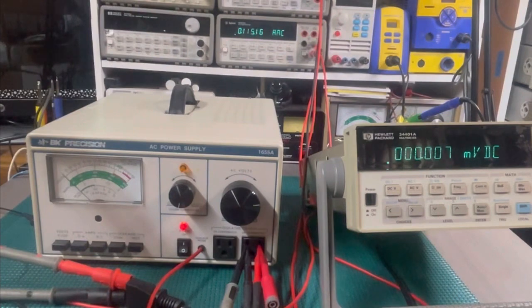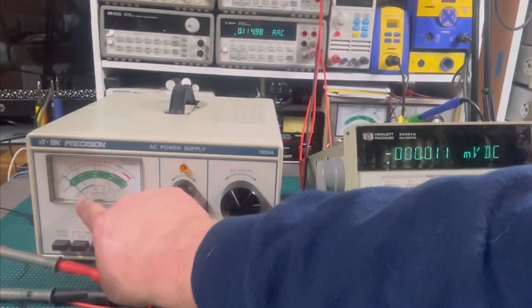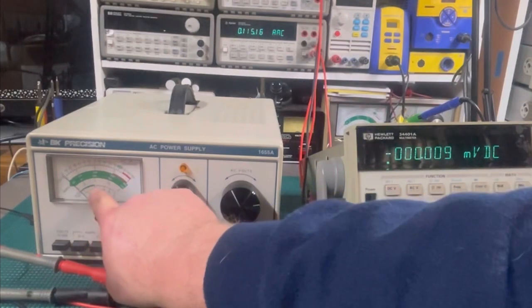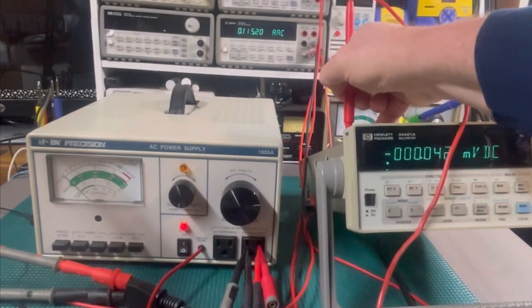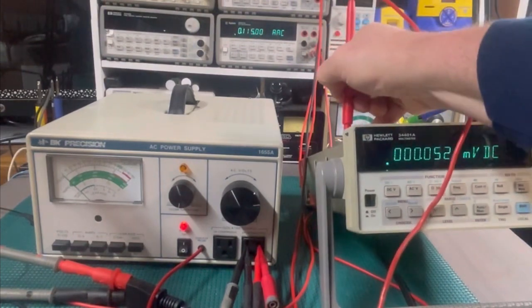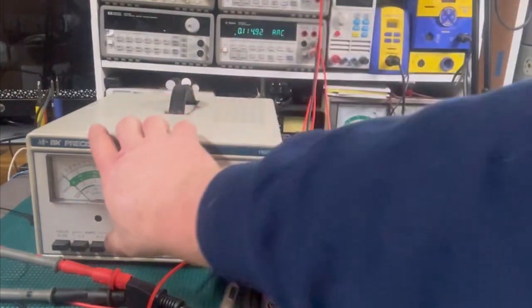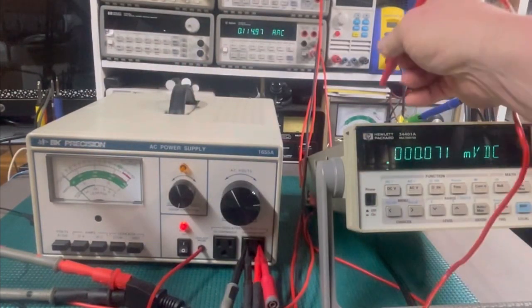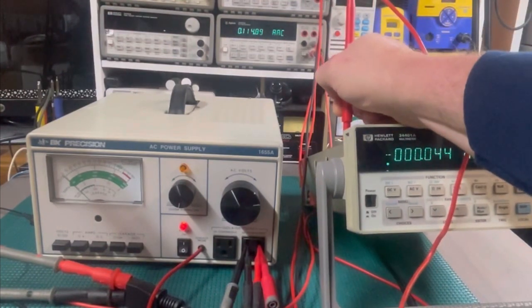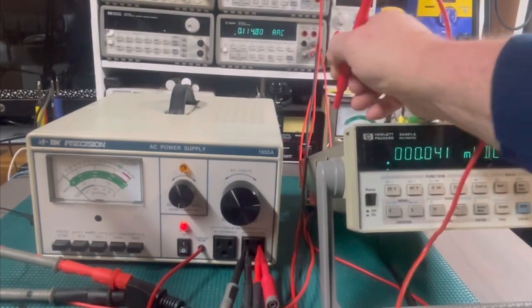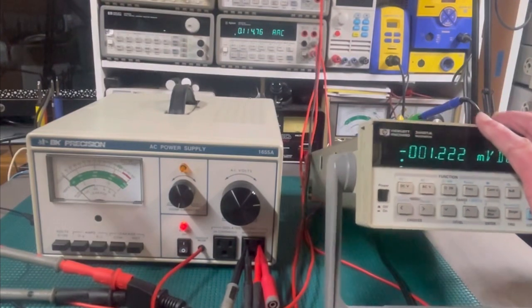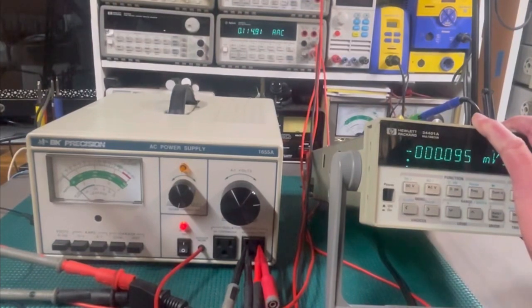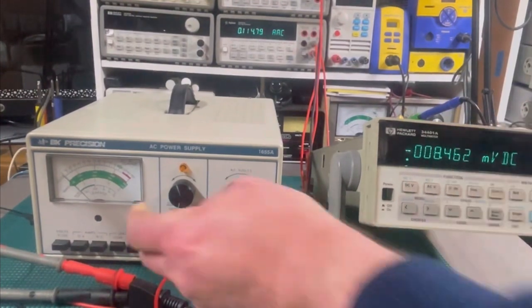But that's not a lot of movement, because if you see how much movement down here, basically your leakage is this graph down here, and this green here should correspond to it. And maybe that's accurate still, even with the voltage up. I don't know, but it doesn't even move hardly at all, so that's good. But let's go to the common, which I assume is the neutral or the white wire. I get this touching. Yeah, there's virtually no leakage. You see it moving ever so slightly. Ever so slightly. Go back to hot.